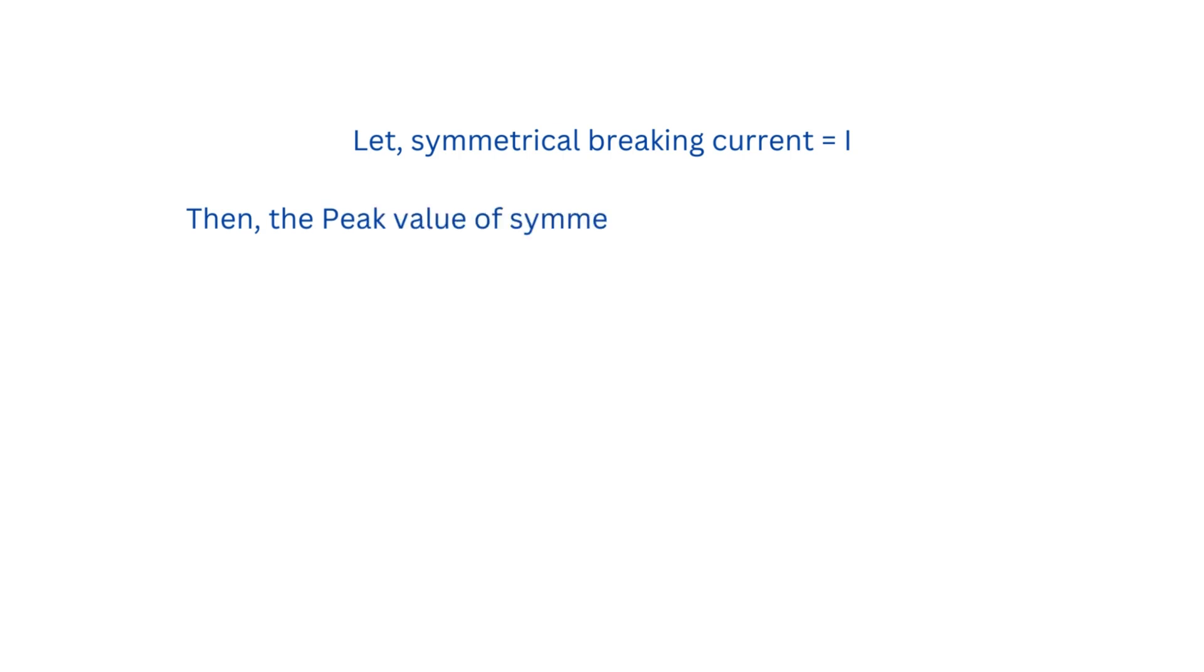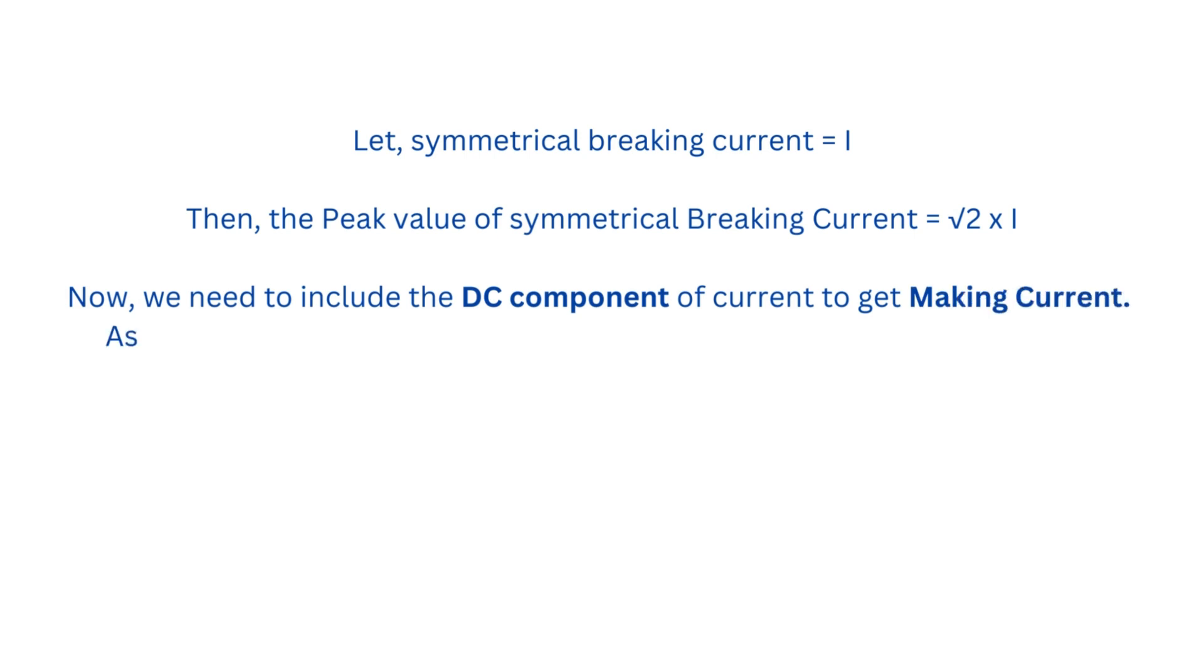To obtain the making current, we need to include the DC component of the current. Since the DC component of the current during the sub-transient state is nearly equal to the peak value of the current, the making current will be root 2 times I into 1.8.